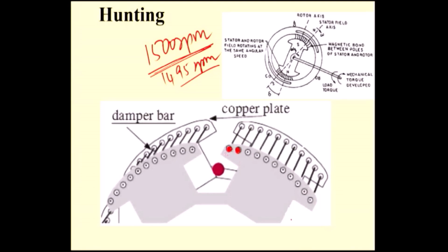Normally, the damper winding is placed in the pole face of the rotor. In the damper winding, EMF will be induced, which produces current. Since the damper winding is short-circuited — a closed path — current will flow. Because of the 5 RPM speed difference between 1500 and 1495 RPM, EMF is induced in the damper winding, which drives the current. Any current-carrying conductor produces its own flux, so the rotor flux increases because of this.